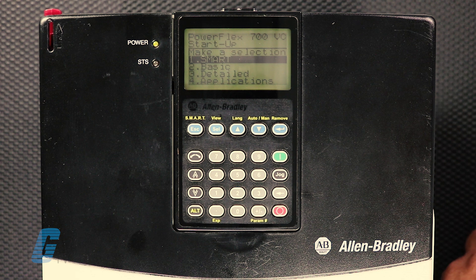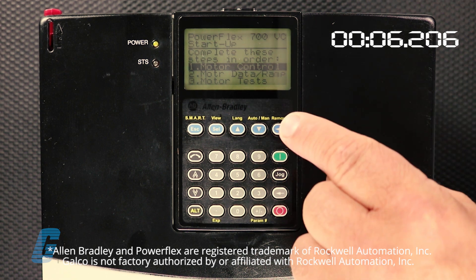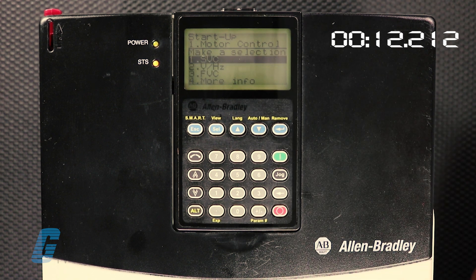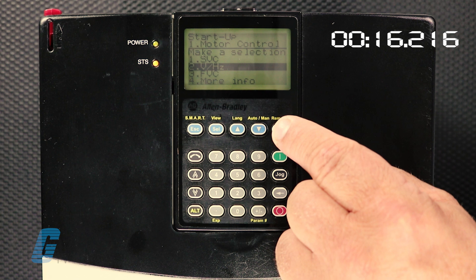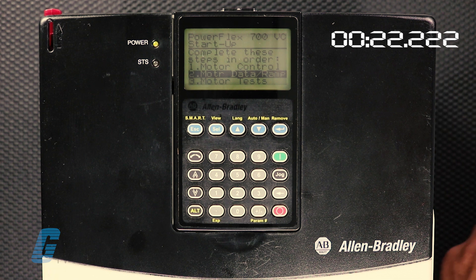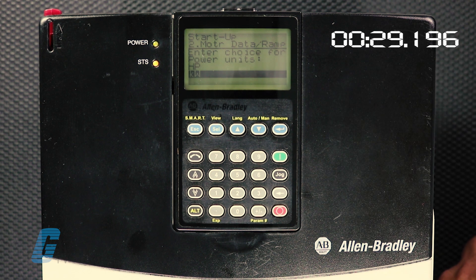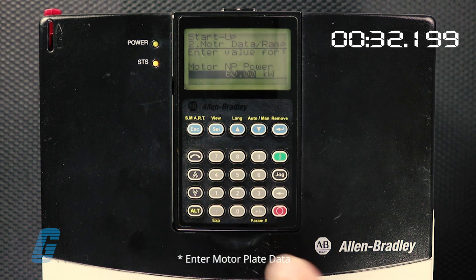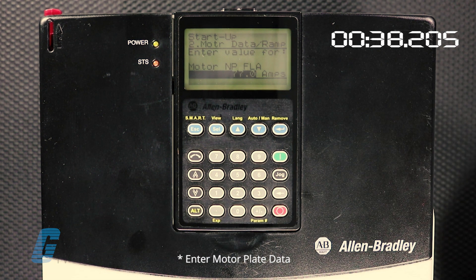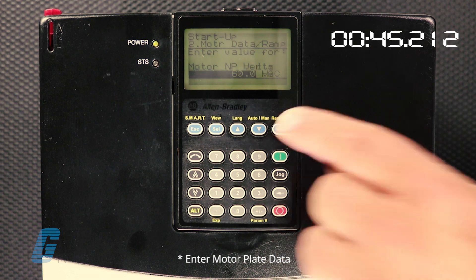Here we go. First, select basic startup. Select motor control. Select the Volts per Hertz option. Select the motor data ramp. Input 0.22kW. Input 0.75 amps. Input 460 volts AC.